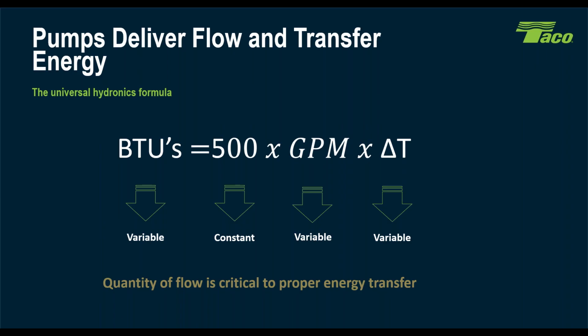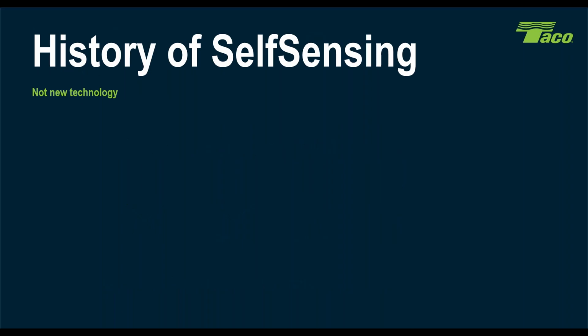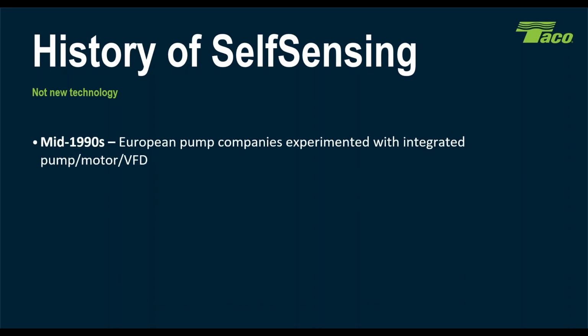And so we use the universal hydronics formula to determine how much flow we need to have based on the BTUs of the system and the delta T that we desire to have. So that's really the crux of everything we talk about within the pumping world. So let's talk a little bit about self-sensing, where it came from, because it's not new technology. I promise it is really not.